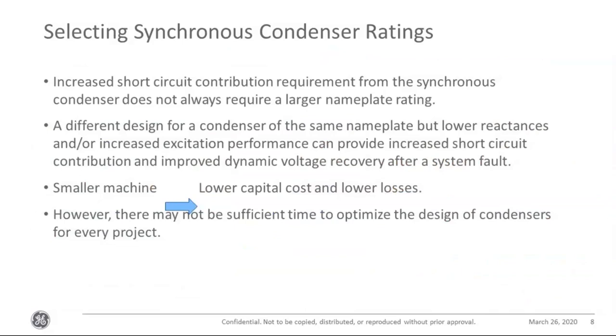Finally, this is something that Nick did mention when he was answering one of the questions. When we talk about synchronous condensers, just because you need a higher short circuit contribution or you need improved dynamic voltage recovery does not mean that you need to increase the nameplate rating of your condenser. That's because the short circuit contribution of the condenser is primarily going to be the internal voltage magnitude divided by your net subtransient reactance, which includes your condenser and your transformer reactance.